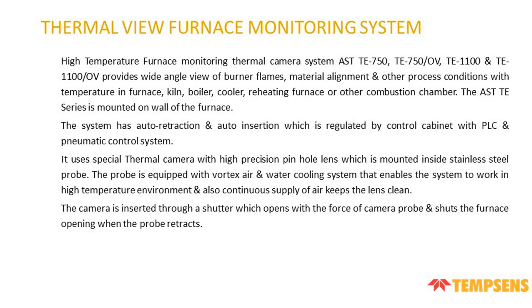The AST TE Series is mounted on a wall of the furnace. The system has the same auto retraction and auto insertion, regulated by a control cabinet with PLC and pneumatic control system. It uses a special thermal camera with a high precision pinhole lens tube which is mounted inside the stainless steel probe. The probe is equipped with a vortex air and water cooled system that enables the system to work in a high temperature environment, and a continuous supply of air keeps the lens clean.